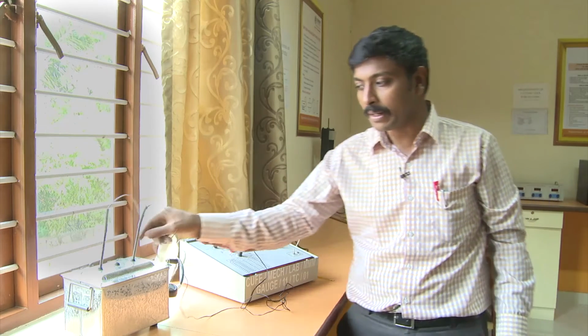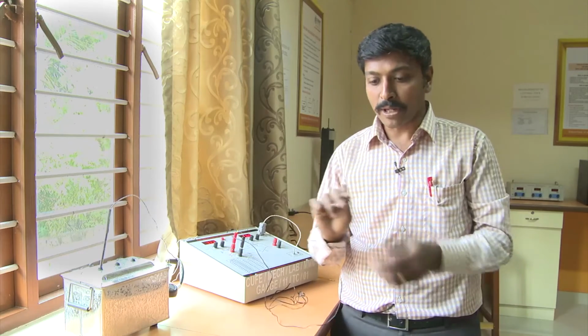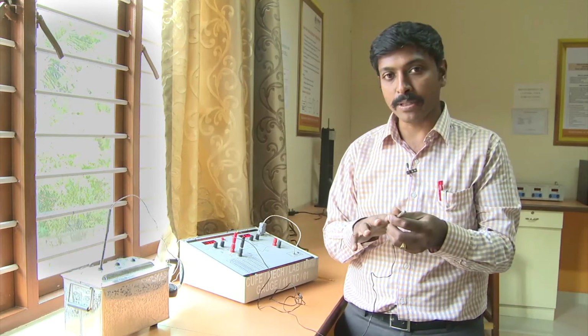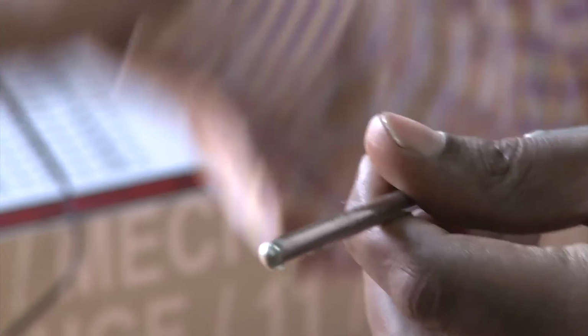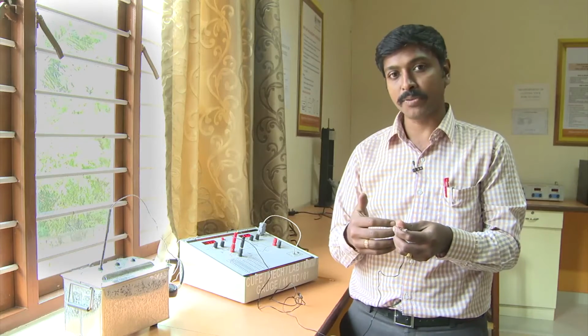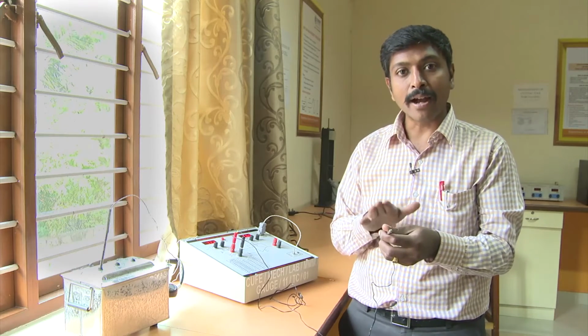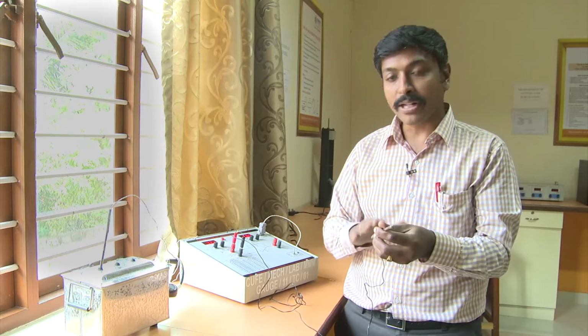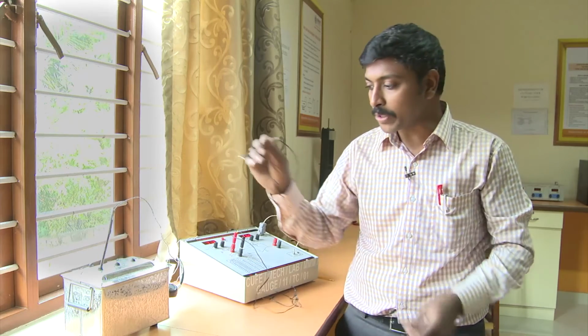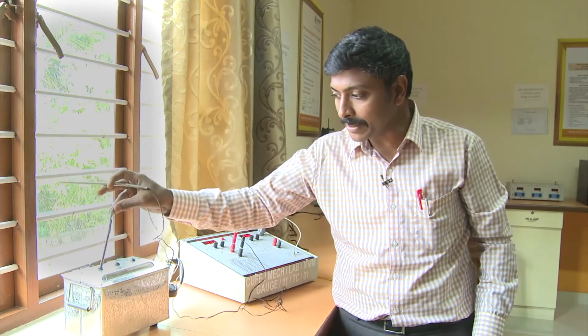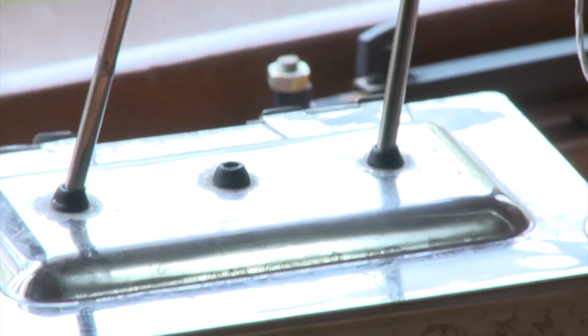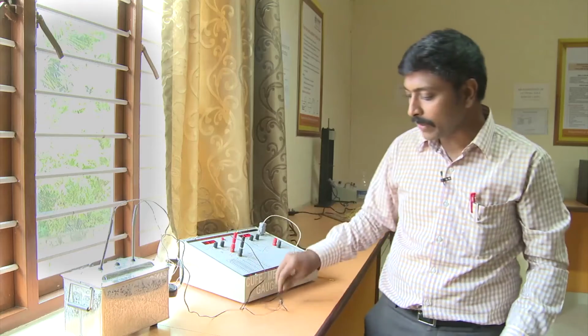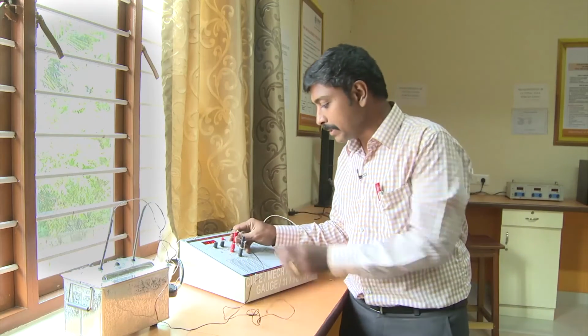So with that, I'm going to compare our thermocouple. What I'm trying to say is that the thermocouple is a variable here. The thermocouple may have some errors inside, inherent errors will be there. So we are going to test how far it has an equivalent efficiency with respect to this equipment named RTD, resistance temperature detector. So the first one we have to insert, and the second one I'm going to insert my thermocouple inside, and this value should also be monitored by these probes.